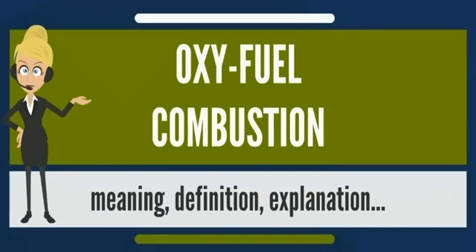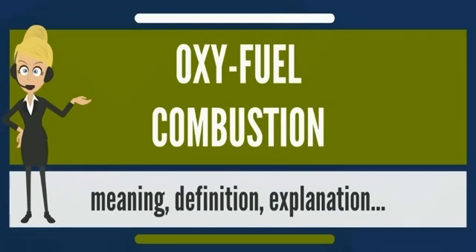The concentration of pollutants in the flue gas is higher, making separation easier. Most of the flue gases are condensable, which makes compression separation possible. Heat of condensation can be captured and reused rather than lost in the flue gas. Because nitrogen from air is absent, nitrogen oxide production is greatly reduced.